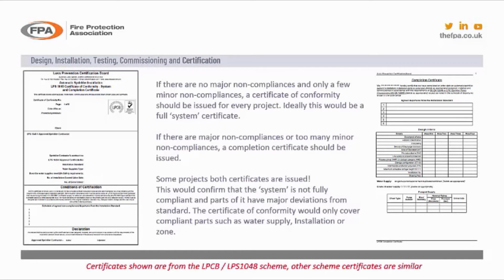Now, can a certificate of conformity be issued? The certificates that I've shown, I'm just reading at the bottom, are from the LPS 1048 scheme, and the other schemes do offer similar certificates. But just for awareness, what you would be looking for, the Shangri-La of certification, is a certificate of conformity, and what you would prefer is a system certificate which captures the whole system. It captures the water supplies, the installation control valves, the zones, everything on the whole system covered under one certificate. It will give you peace of mind that you've got a fully compliant sprinkler system.